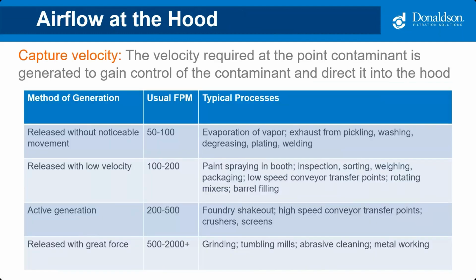When determining the required airflow at the hood, the main design factor is called capture velocity. This is the amount of air required to reach out and grab the dust where it's generated and gain control of it and direct it to the hood and through the duct. The main goal here is to keep the operator safe and keep the particulate away from his or her breathing zone. The chart shows a general rule of thumb for capture velocities. It ranges from very low levels for very light floating contaminants to high velocity sprays of dust.